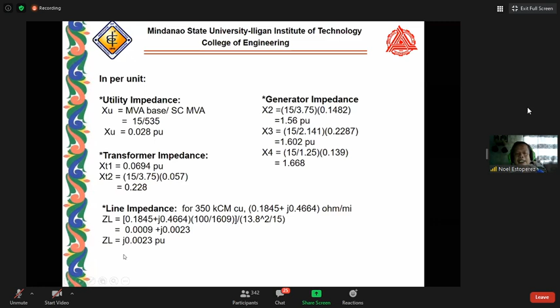So how will we determine the fault at bus 1 at the 69 kV side? For bus 1, this is the equivalent, with a default 1.0 pre-fault voltage. We should know the equivalent positive sequence impedance looking at the fault point. Looking at bus 1, we have XU, and on the other side, XT1, ZL, XT2 which are in series. Then this combination is in series with the parallel combination of X2, X3, and X4 of the machines.